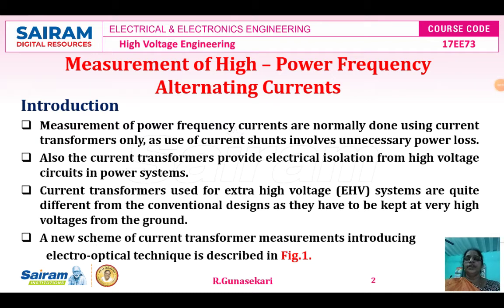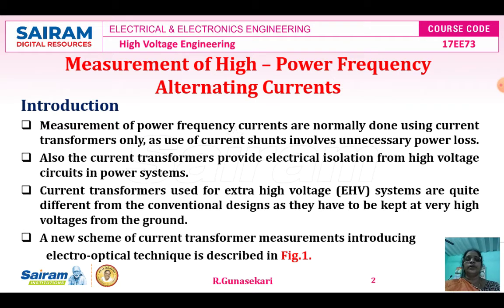We studied the introduction to measurement of high power frequency alternating currents. The measurement of power frequency current is normally done using current transformers only. The use of current shunts involves unnecessary power losses in the measurement of high power frequency AC current.